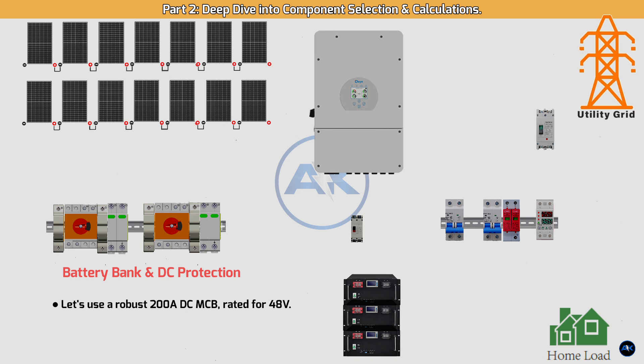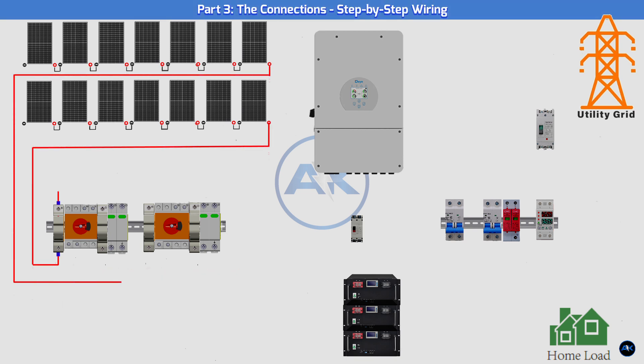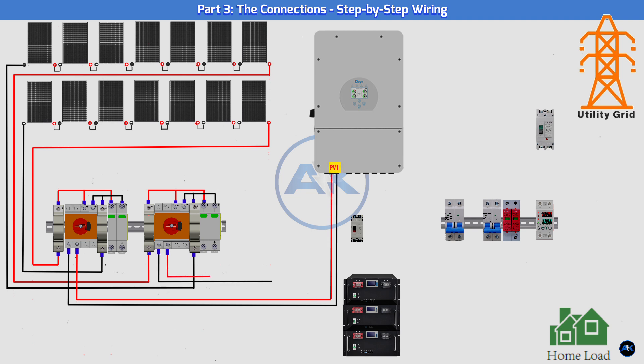Part 3: The Connections — Step-by-Step Wiring. PV strings: connect the positive and negative MC4 connectors from your first string to the first input of the DC combiner box; repeat for the second string. DCDB to inverter: connect the output of the DC isolator to the PV input terminals on the Deye inverter.